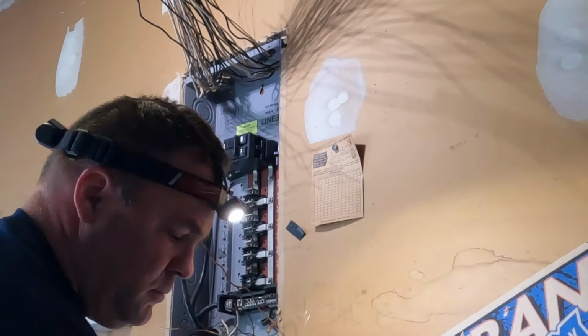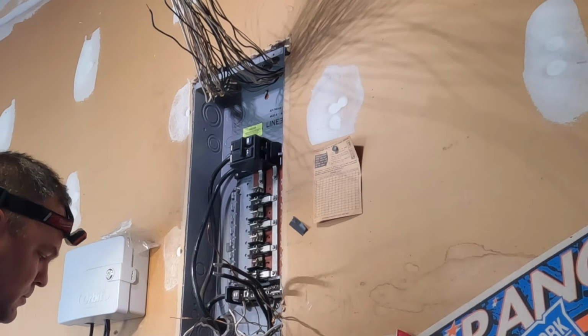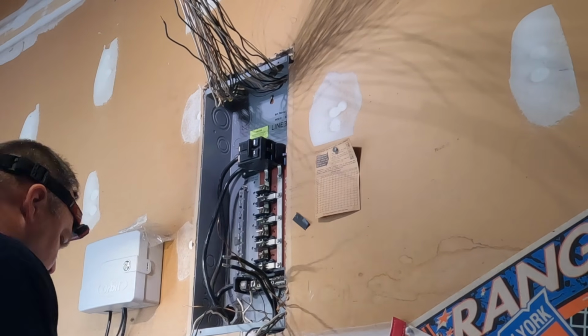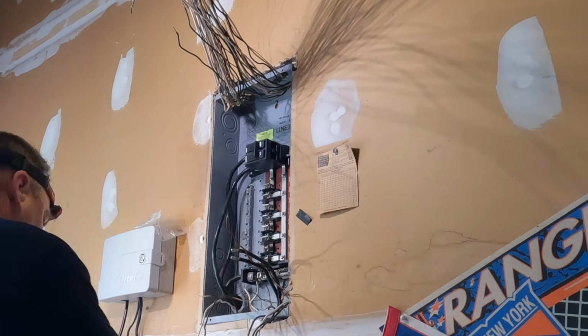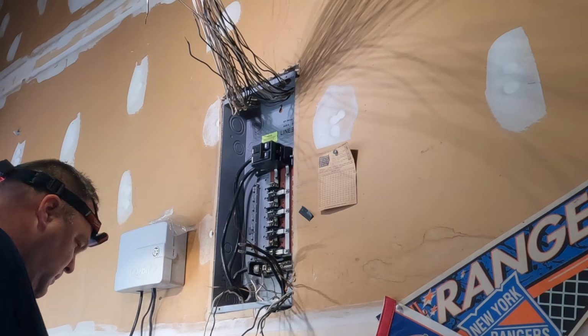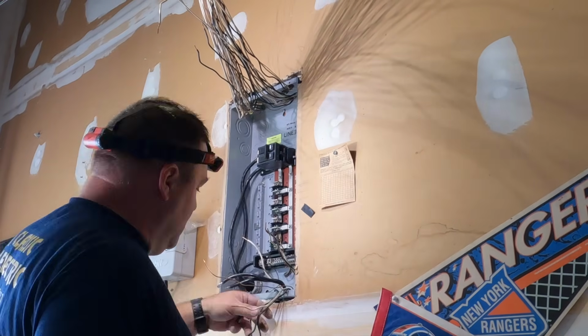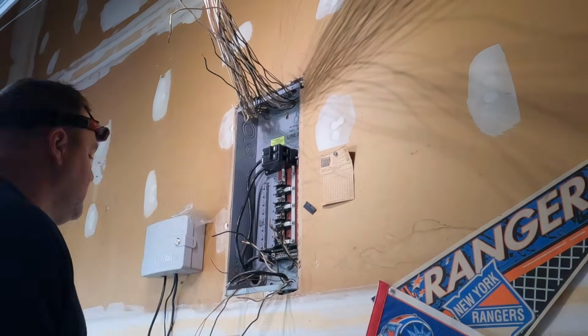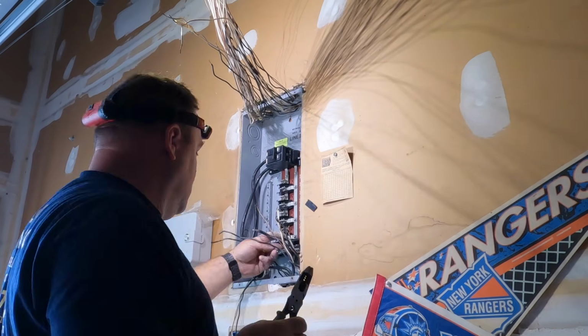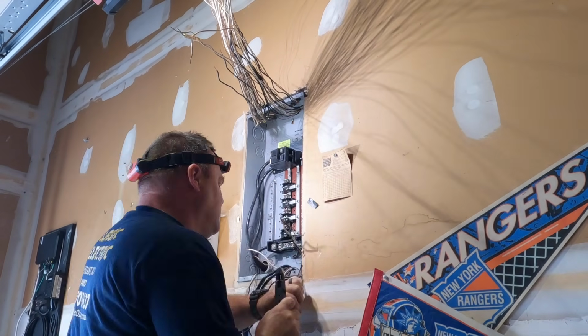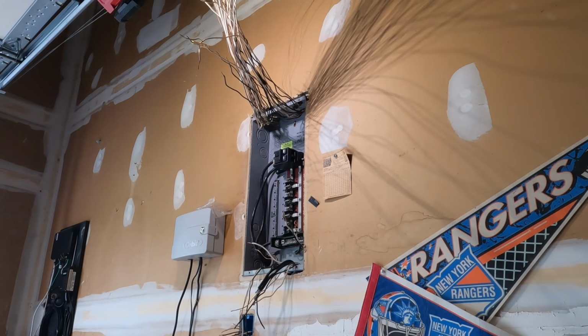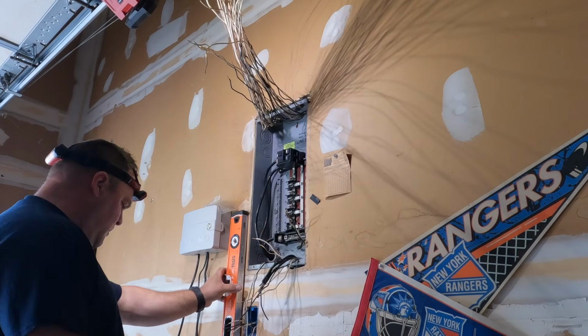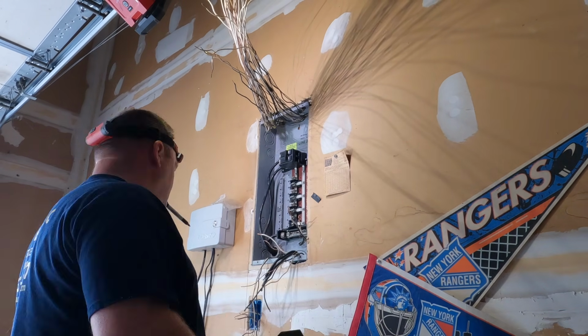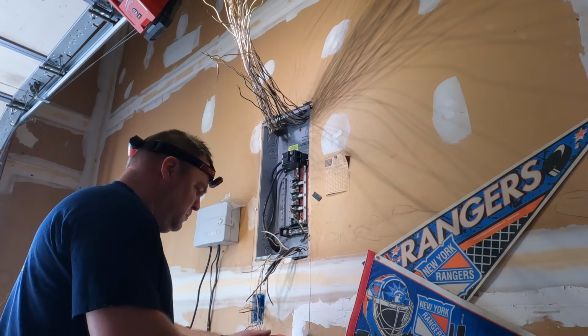No connectors at all, that bothers me. Just get a connector in there somehow, whether you've got to open up the sheetrock or not, so it's connected properly to the enclosure. The sharp edges when you make the opening could damage the conductor. I can't say I haven't seen that, but I don't see it too normally, so I would definitely put a connector in there. I have to, I'm a licensed guy. I cannot put something in with no connectors.